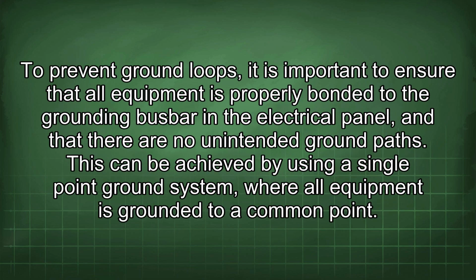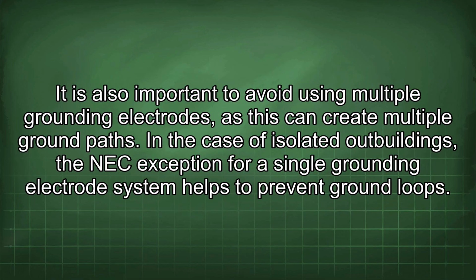To prevent ground loops, it is important to ensure that all equipment is properly bonded to the grounding busbar in the electrical panel and that there are no unintended ground paths. This can be achieved by using a single-point ground system where all equipment is grounded to a common point. It is also important to avoid using multiple grounding electrodes, as this can create multiple ground paths. In the case of isolated outbuildings, the NEC exception for a single grounding electrode system helps to prevent ground loops.